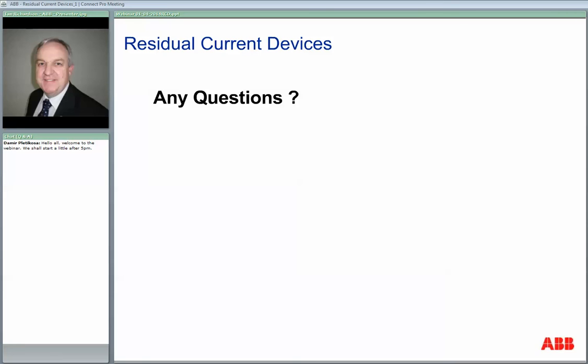Does an RCD tester require calibration? Yes, it should. Most of the devices are pretty good, and they'll give you an indication. If you're working with a calibrated device, you're obviously working with something that you know the situation with. So if you're a professional contractor and you're using your device for testing and literally making recommendations on a circuit, I would suggest that you should be looking at yearly calibrations. So it's certainly a wise thing to do.